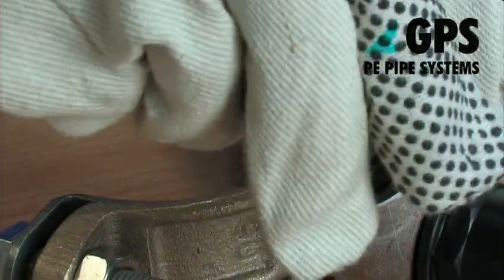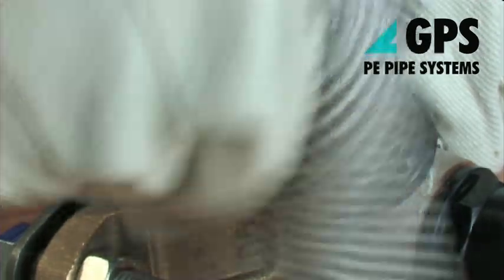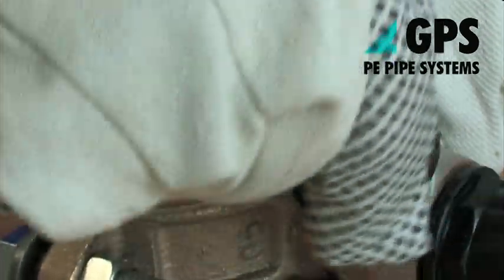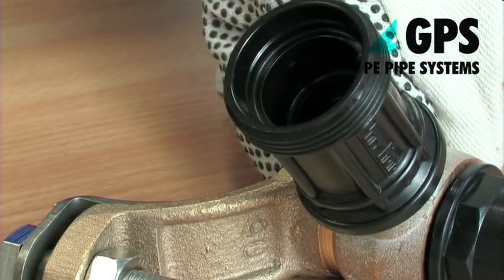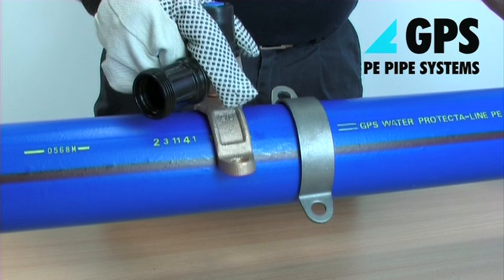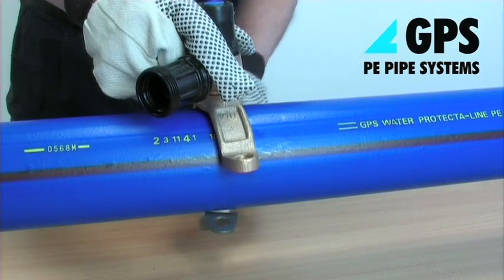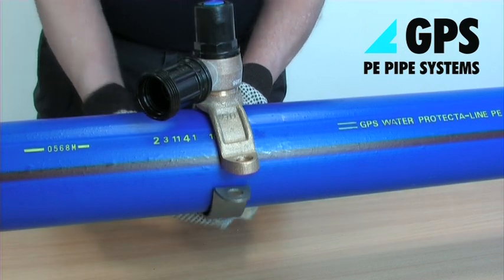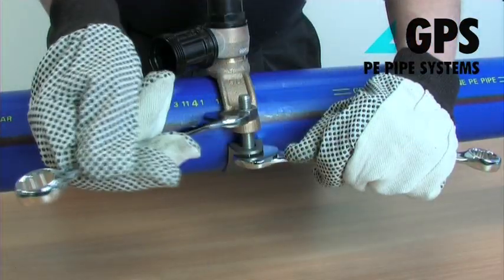Fit the Protecta-Line end connector compression fitting to the ferrule strap male outlet, employing sufficient PTFE tape to ensure a good seal. Clean the surface of the Protecta-Line main where the self-tapping ferrule strap is to be installed, avoiding areas which appear damaged. Fit the self-tapping ferrule squarely around the main and tighten the two strap bolts evenly and symmetrically.